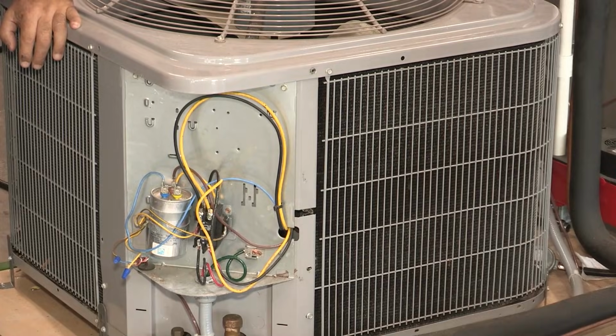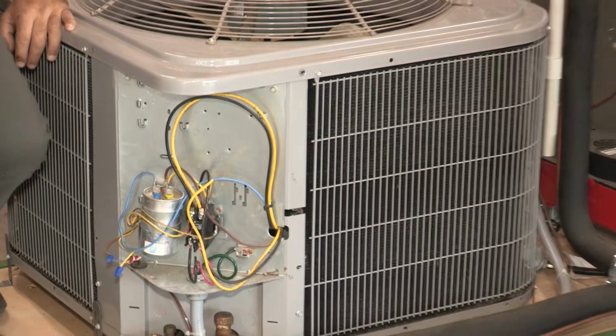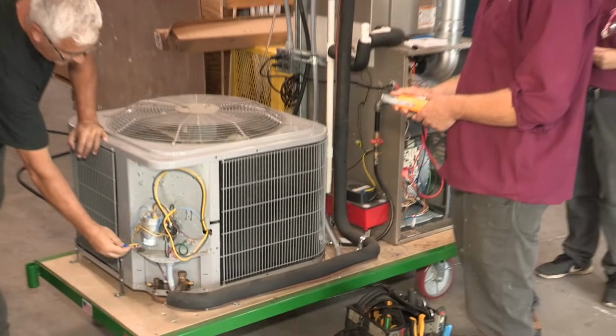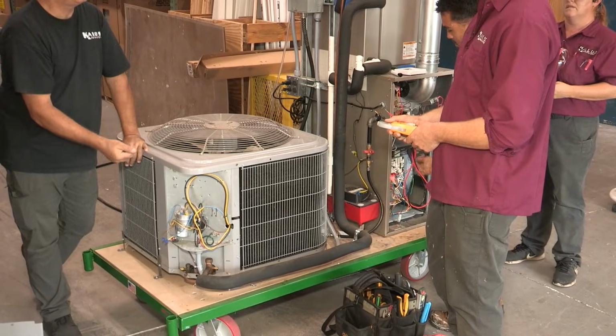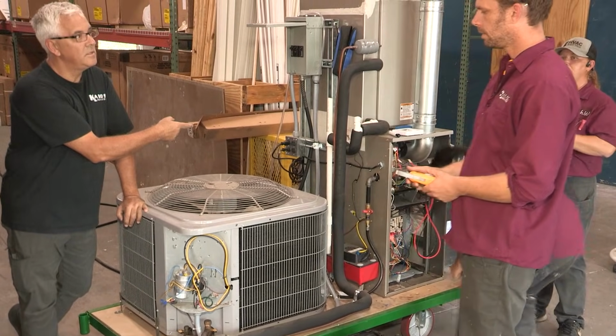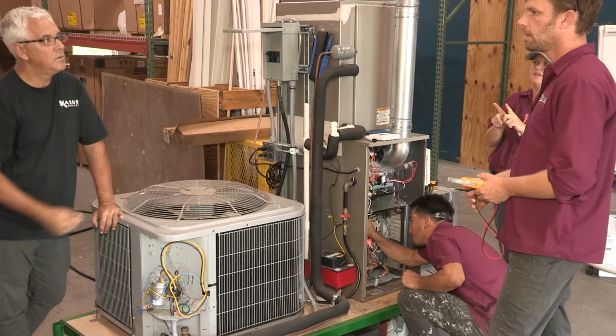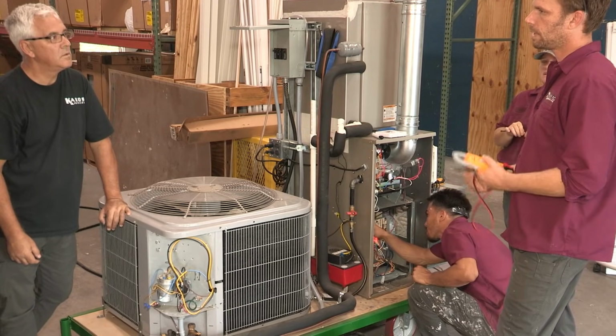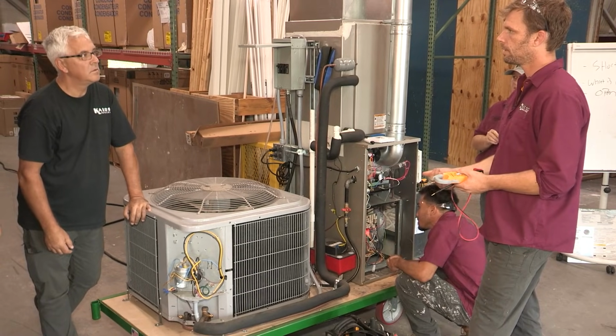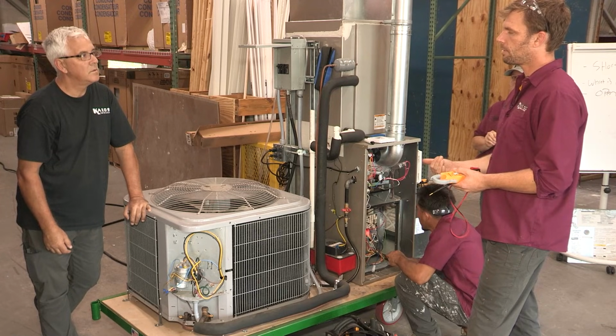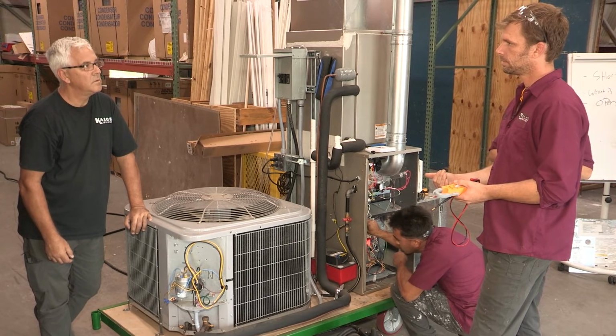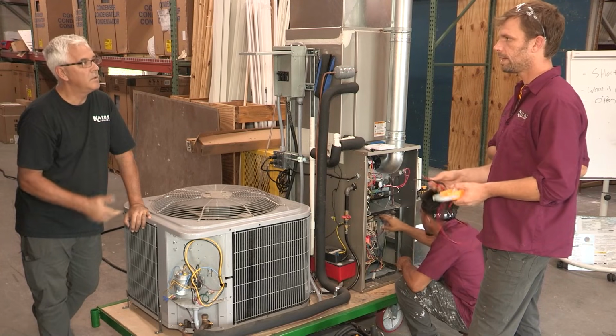Why don't we use the meter to try to isolate where this short might be? Can we do that by tying the wires together like you said before, and then test with continuity? Nope, we're not looking to see if we have continuity. We know we have a path already, we just have a path to the wrong spot, which is most likely ground.